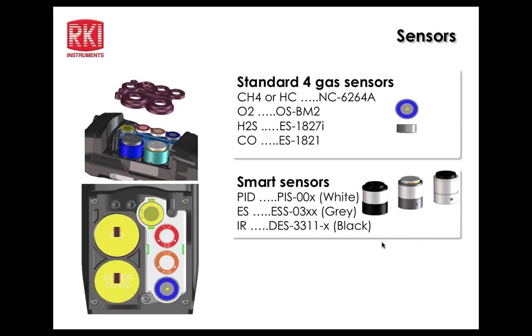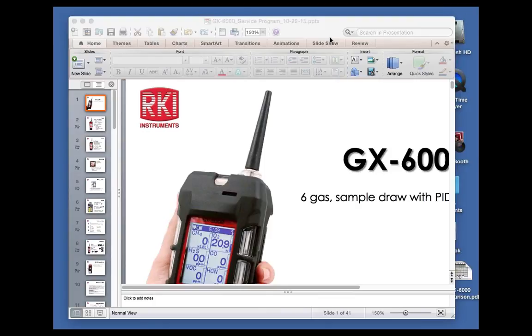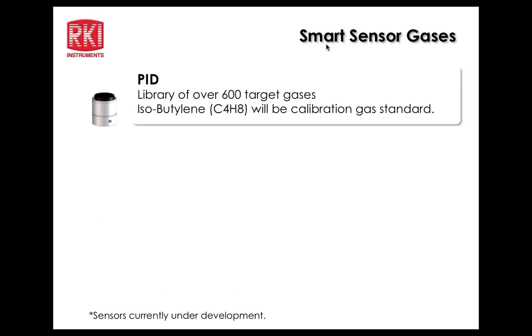John Maslowski says he was told we can use 2 PIDs in this unit, and does the position matter, high and low? I don't know, Bruce, do you have an answer? If you were going to use 2, and I believe you can, you'd want to put the low range in the first slot, since that's where you want the greatest sensitivity. As far as the 2 agreeing perfectly together, they may not, because in low ranges, say below 50 ppm, they may not agree. Right, so the customer would just have to realize that.